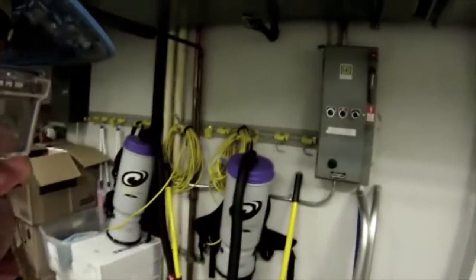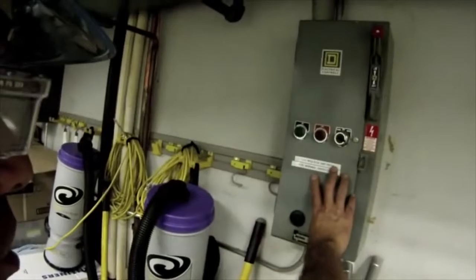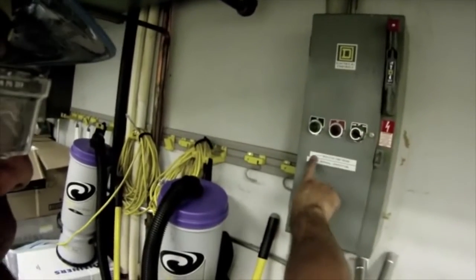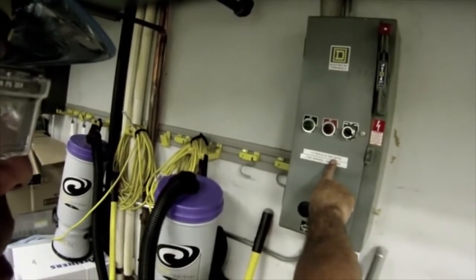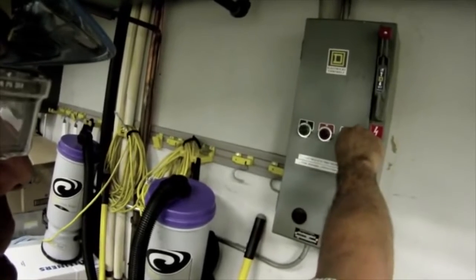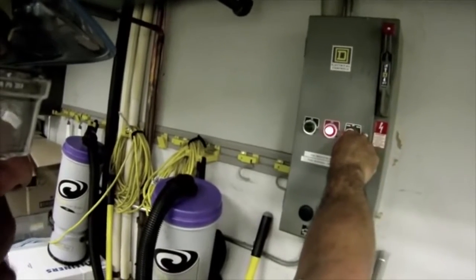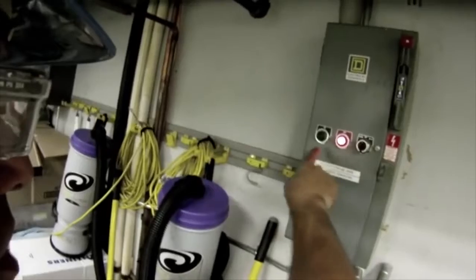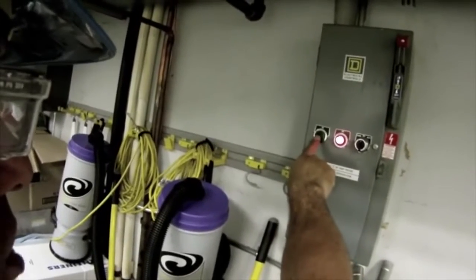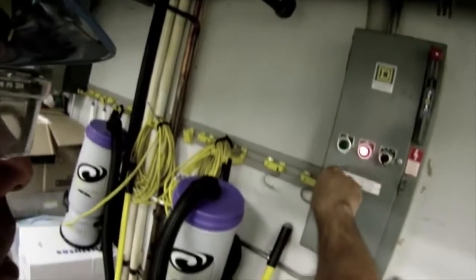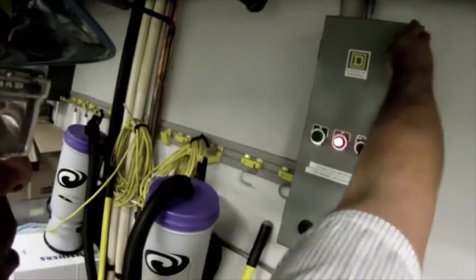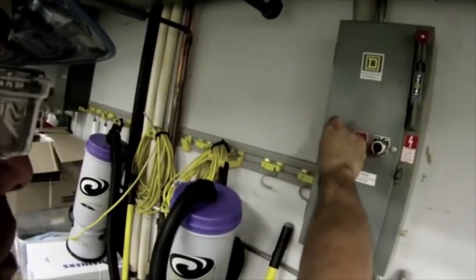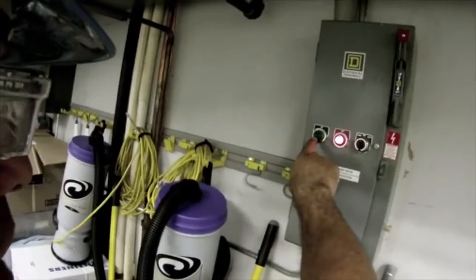The first thing that I want to do is de-energize power. My starter contactor is here against the wall. Obviously, this contactor works in the hand position all the time. That's its design, and so I'm just going to shut that off. I noticed that I didn't have a light in the on position, so I'm going to note that. Later on, after I de-energize this, I will pull this apart and replace the operations light.